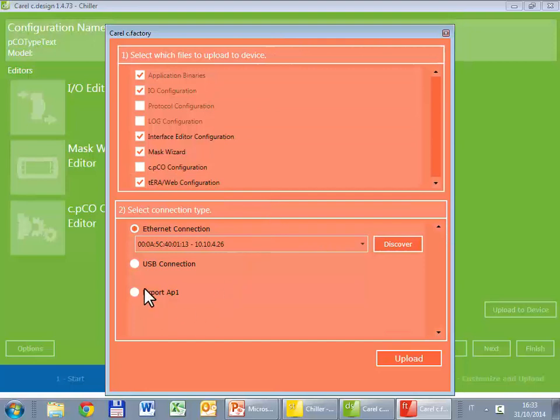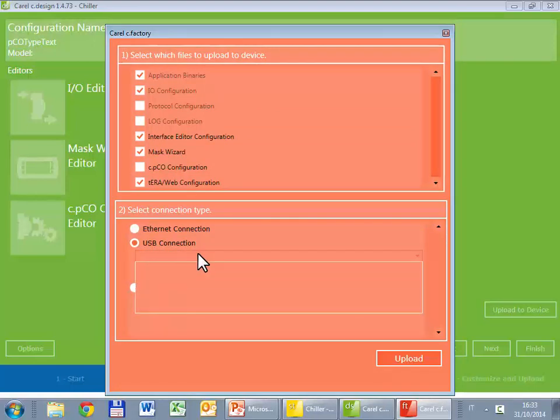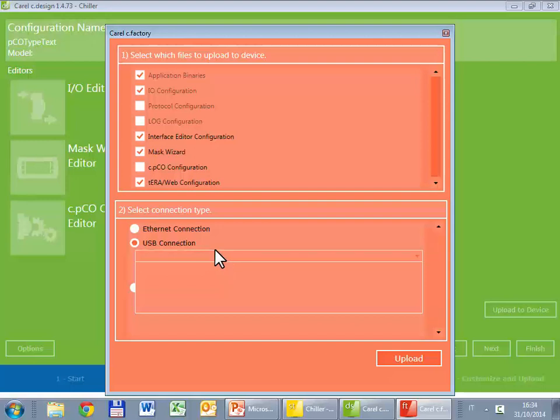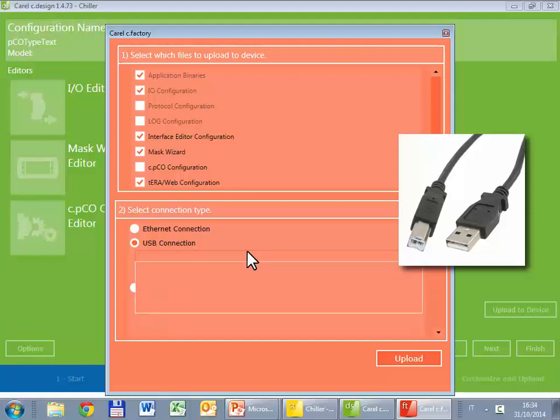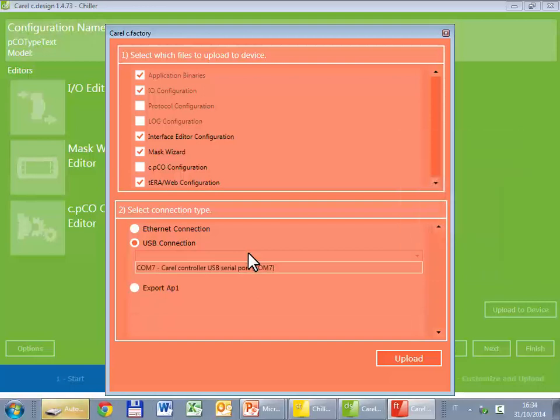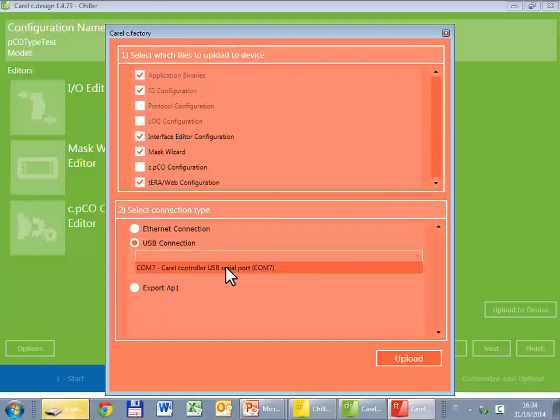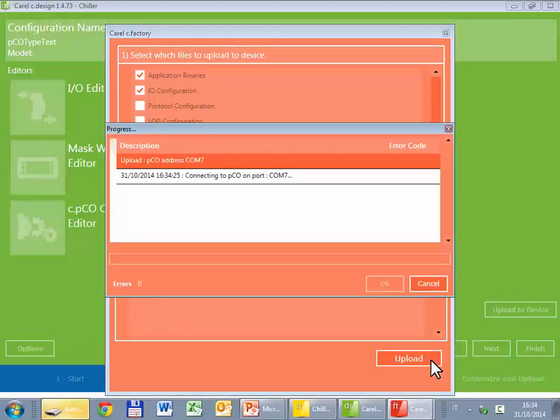We can start with the USB connection. We have to drop down the list and select the COM port corresponding to the pCO. The list is empty because I have not already connected the pCO to the PC. I am doing it right now. You may need to wait for the installation of the driver. Here it is, Carel controller USB serial port. Very good, and then upload.